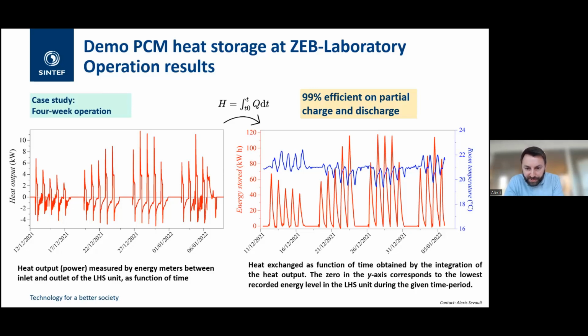But the interesting part of this graph is that even though we do partial charge and discharge, we always come back to zero. That's quite interesting, because you could think that if you don't do a full charge of the system, you might not be able to recover everything that has been stored, because the heat could be just a little bit more dissipated and hard to recover to the heat exchanger. But it actually works pretty well. It's really reversible even in partial charge and discharge. So it's been very satisfying to prove it.